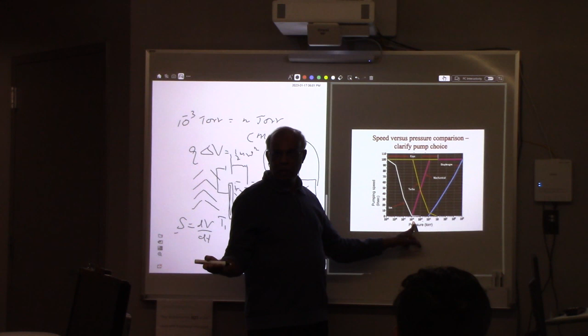So these are mechanical pumps. They don't change much until you reach a kind of low pressure, and then after that their speed pretty much goes down. They cannot do anything, because after this point one of these other pumps has to pick up. If they have high speed, then you should get lower pressure. Mechanical pumps cannot work even at 10 to the power minus 3, which we call 1 micron or 1 millitorr. After that they're almost dead.